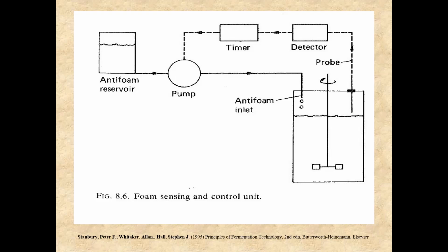Now you would say that there is a probe, we understood, that is the main component. There's a detector that will detect the current and that will activate this pump so that the antifoam flows through this pipeline for a few seconds. Why is this timer incorporated into this system? It has a very important role to do.